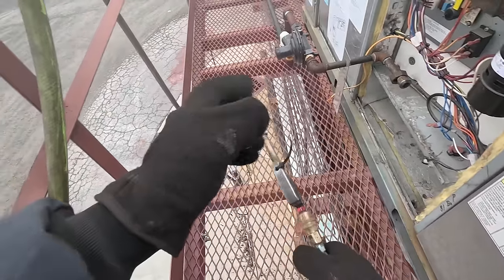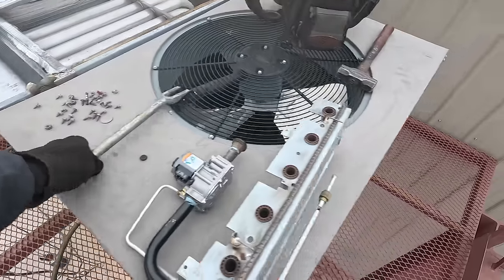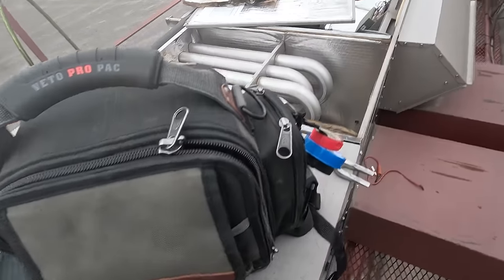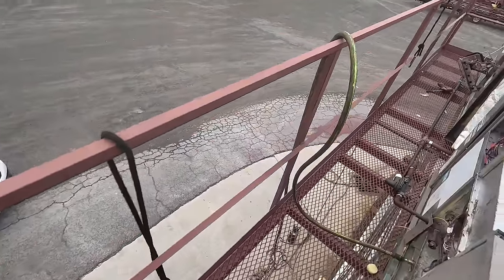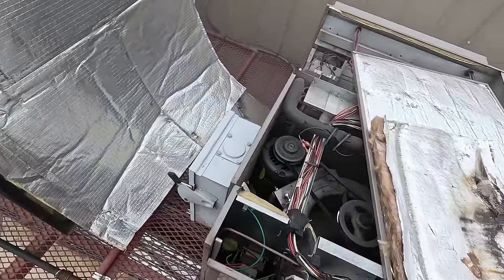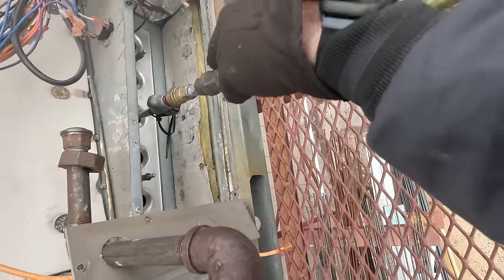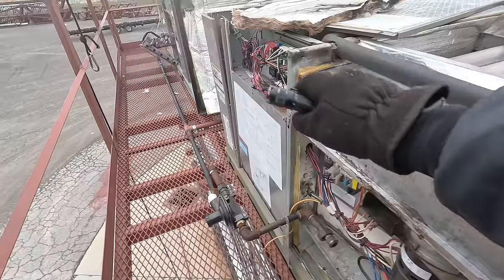Broke some crap loose. What we need to do is put a piece of tape on the spray nozzle, stick it in there, and pound on it — or a wire tie might work too. There goes that blower motor again — shot. What's the point of even working on it? I probably got a centrifugal switch in there. Go ahead and wire tie it like that, stick it in there, and let's pound on this thing and see if we can get some stuff to come out of it. Yeah — look at that. Most part, I got a good push and got a good majority of it out of there.